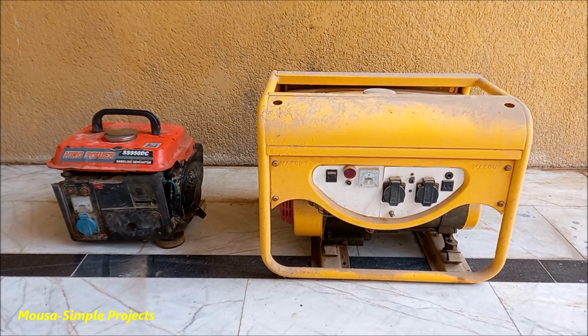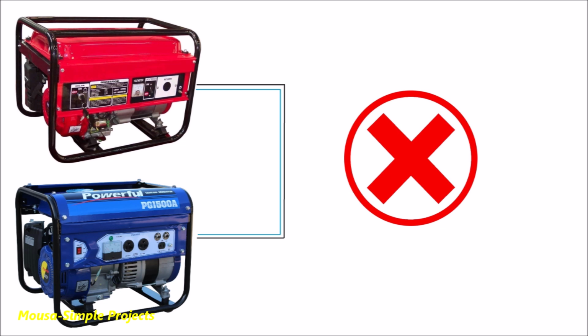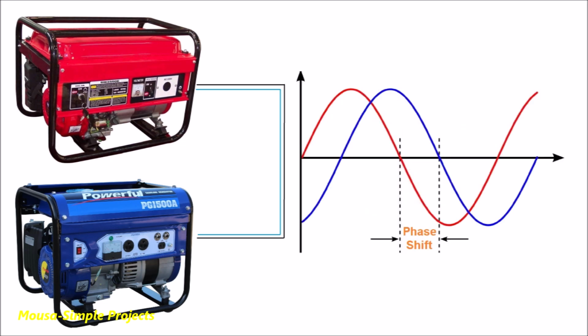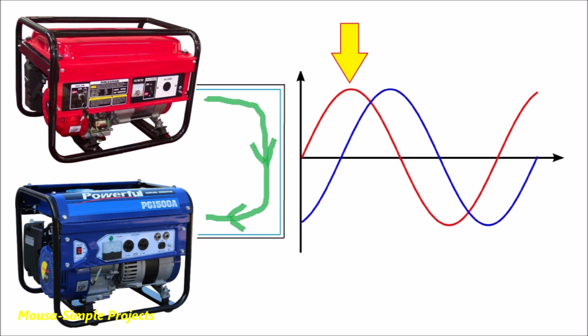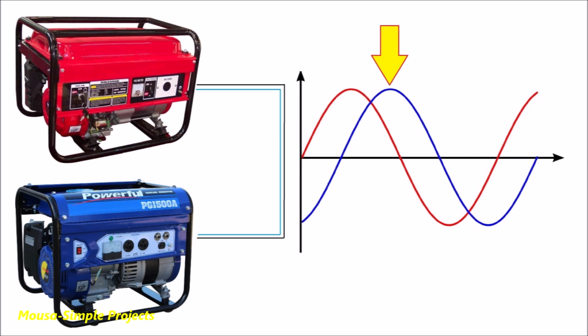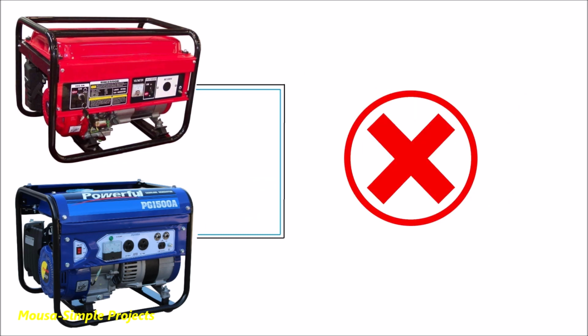Let's say, for example, you have two gasoline generators and want to connect them together to increase the output power. In this case, you can never hook them up in parallel because there is a phase shift between the two output waveforms. At this moment, the voltage of the first generator is higher than the second, so current, instead of going to the load, starts to flow into the second generator. That means the second generator is loading the first one. At another moment, the first generator loads the second one instead. So they can damage each other. This is why you cannot connect two generators without synchronization.